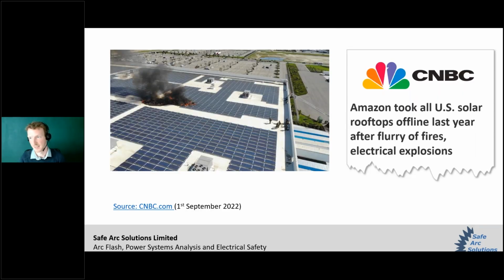To illustrate that solar is one area of concern, this was reported very recently by CNBC in the States: Amazon shut down all of its North American rooftop solar systems in June 2021 after experiencing arc flash events at 6 out of 47 sites over a 12-month period. Subsequent investigations found issues with the design, installation, and maintenance of these systems, which were leading to these arc flashes and fires. Amazon themselves estimated that each of those 6 incidents cost around $2.7 million to investigate and rectify. So these are not small issues, and they're affecting big companies.